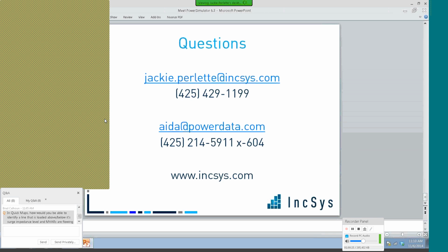One of the other questions was, if the unit's in manual, how can it have any reserve? Because that's the way it calculates it. Right now, it doesn't actually take into account the operator. It doesn't take into account what mode the unit is in. It just looks at what the max of that unit is and compares it to what it's actually scheduled at. So it doesn't take into account if it's in manual or in LSD, but that's something that we can maybe look at in the future. It just gives you the capability of what you could have.